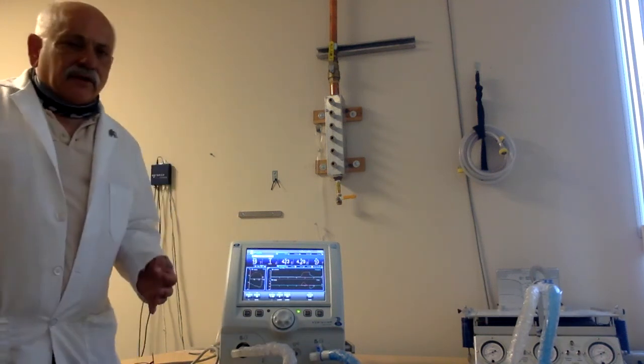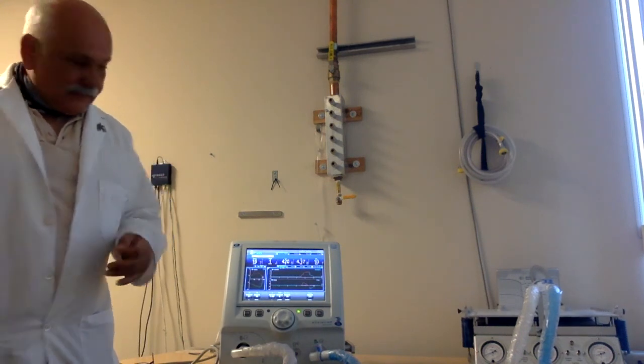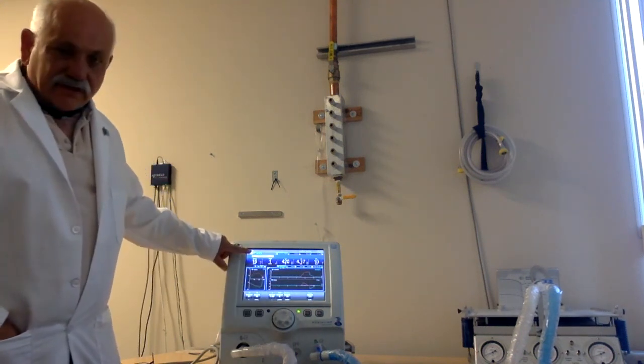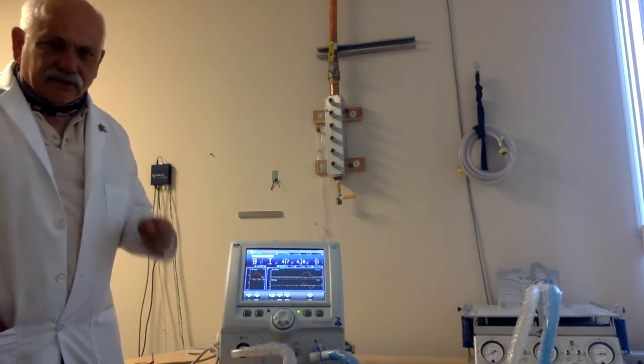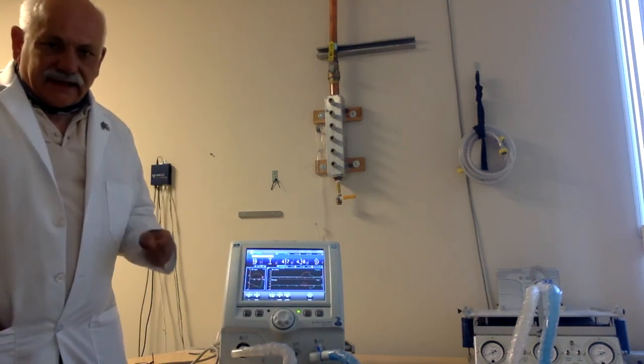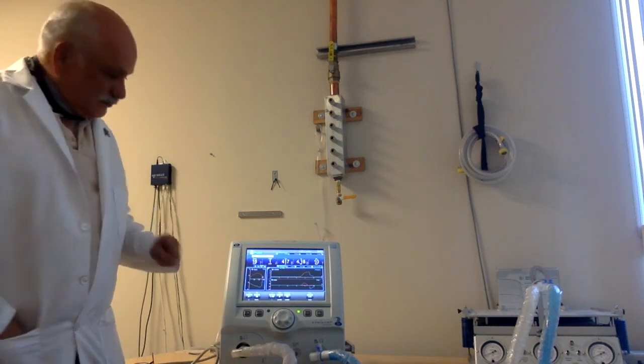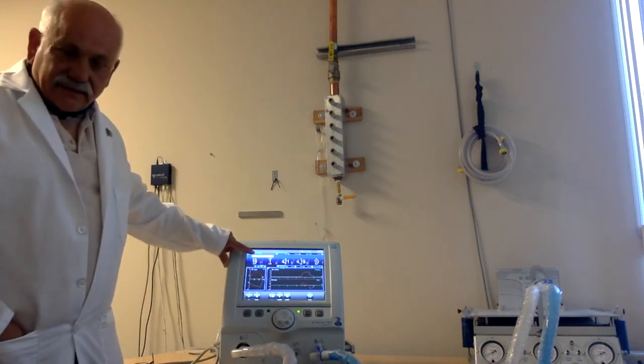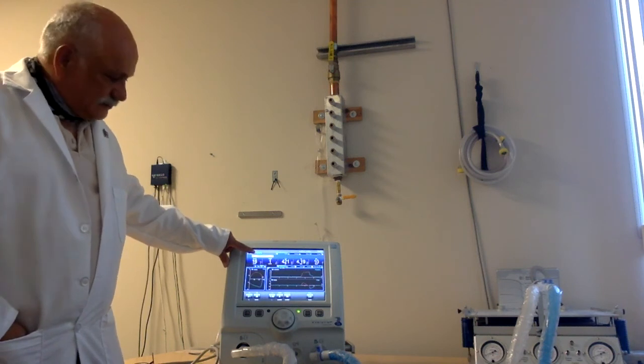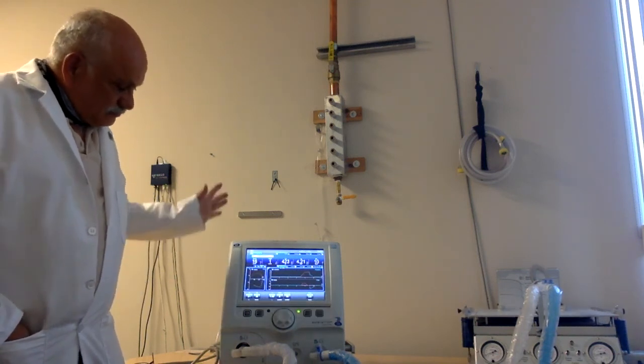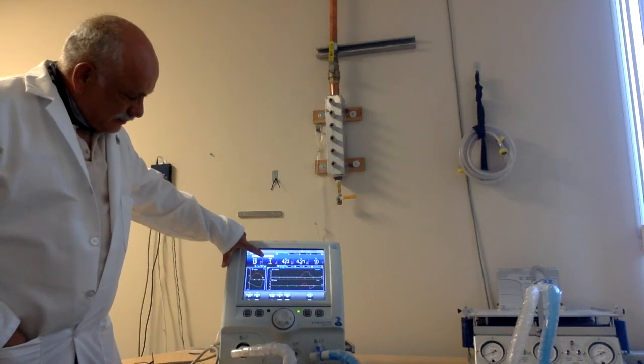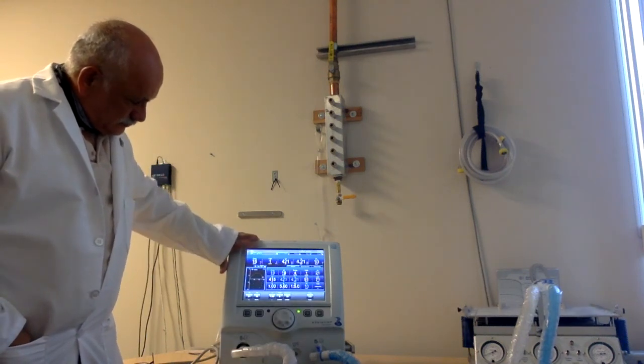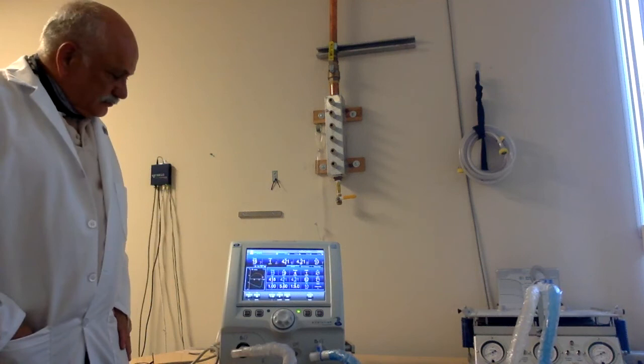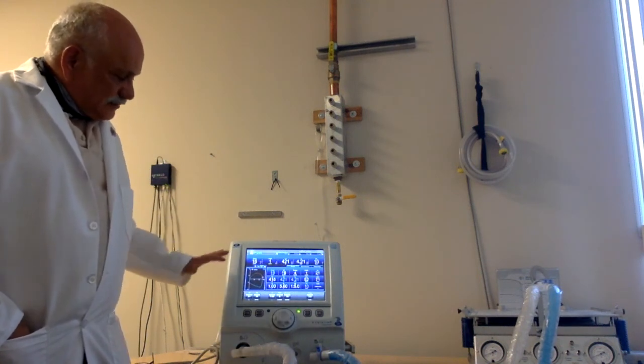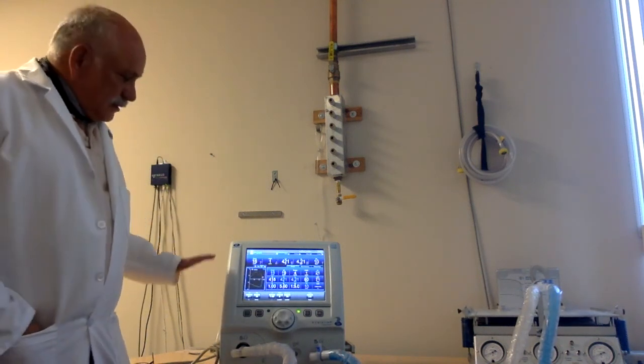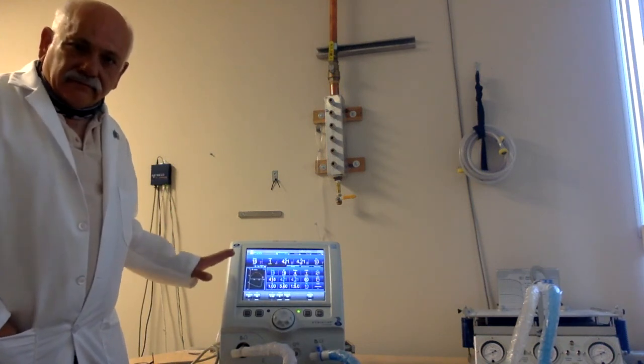But if an alarm occurred while you were away from the bedside, you're still presented, when you come back, a latched alarm. Again, these are the critical features that you'll find in an intensive care ventilator. It's telling me that there was a low PEEP occurrence and that it was adjusted. I know that, so I can clear it by simply touching. And away it goes. So these are the features I love in an ICU level ventilator.